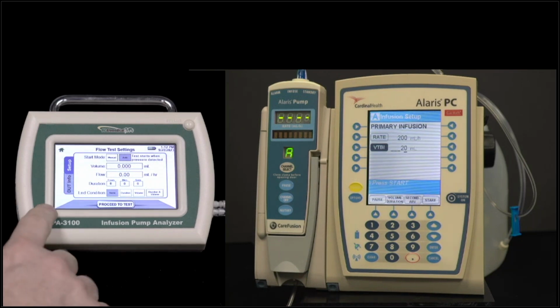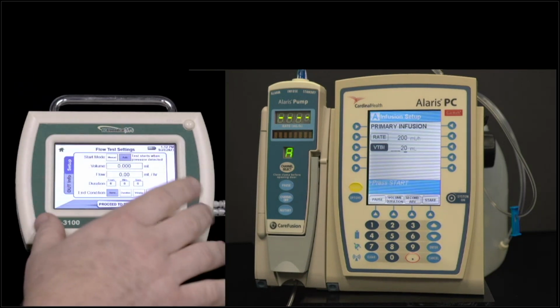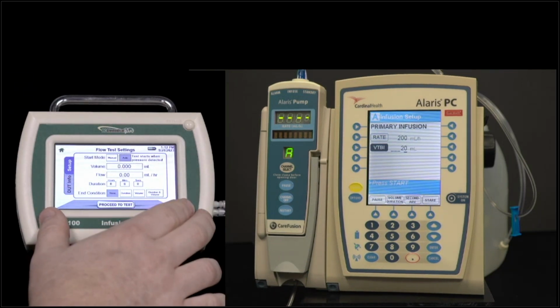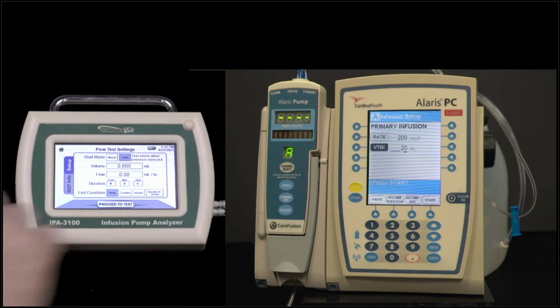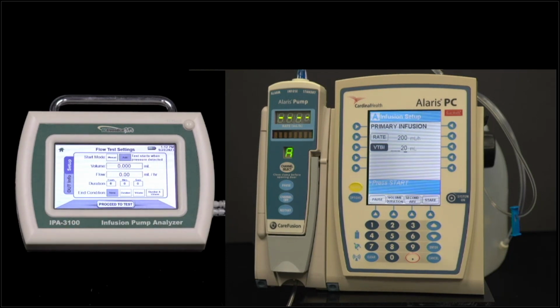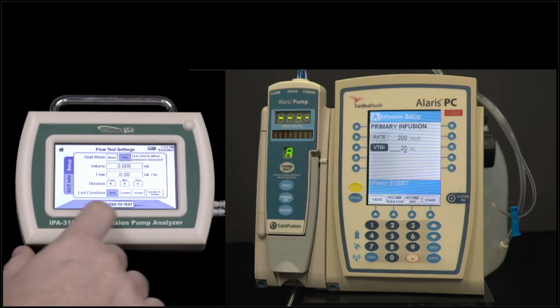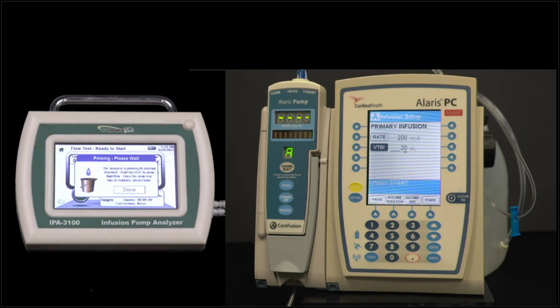Now, on the IPA-3100, I have a similar configuration screen. Now, if I just want to take measurements and get a flow rate and get a volume delivered, I don't have to worry about setting the volume or flow. I don't have to worry about setting the duration. I can just go right into my testing and get measurements. So I'm going to show that here real quick. So we're going to proceed to the test.